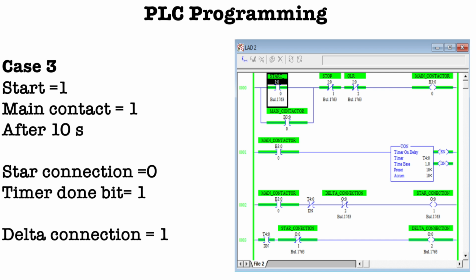So in this case, when I press the start switch, my main contactor gets the supply and my timer starts counting for the 10 seconds. For the 10 seconds, my motor is connected in the star connection, right?